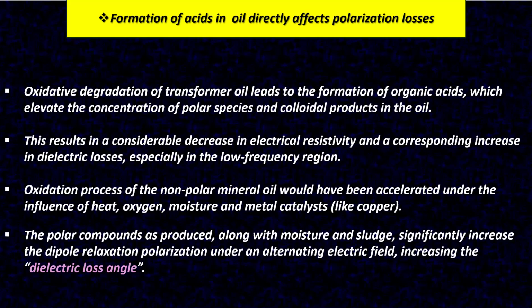The oxidation process of the nonpolar mineral oil is accelerated under the influence of heat, oxygen, moisture, and metal catalysts like copper. The polar compounds produced, along with moisture and sludge, significantly increase the dipole relaxation polarization under an alternating electric field, increasing the dielectric loss angle.